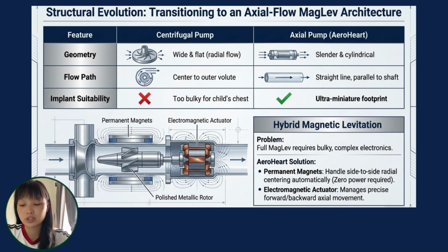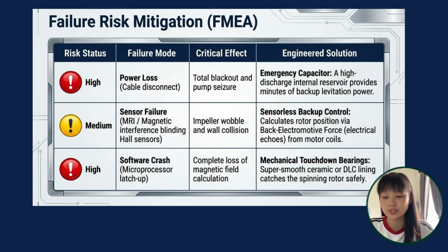Lastly, the levitation strategy also needs to be reconsidered in order to fit this smaller scale. Therefore, we use a hybrid approach. For the hybrid approach, there are two parts, which are the permanent magnet and the electromagnetic actuator. As for the permanent magnet, the job is to keep the impeller centered side to side. The benefit of this permanent magnet is that it does not need any wires or batteries. Next is the electromagnetic actuator. A small electromagnet acts like a smart pilot, and the benefit of this is it only uses energy when it needs to move the impeller, keeping the device small and cool. So now we will talk about the risk analysis.